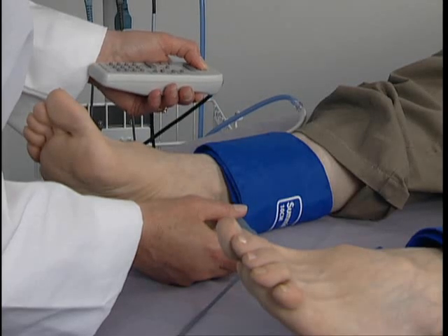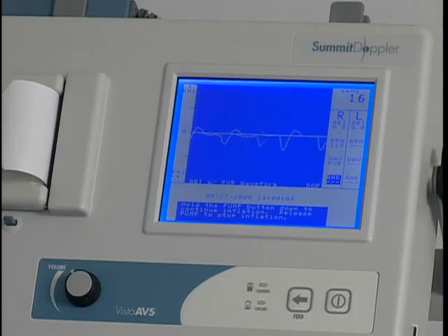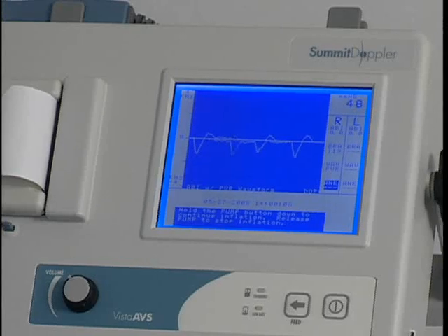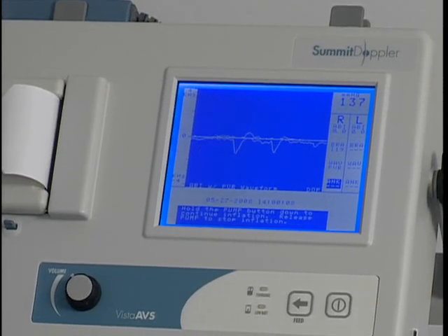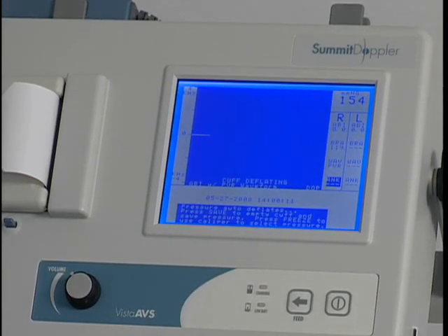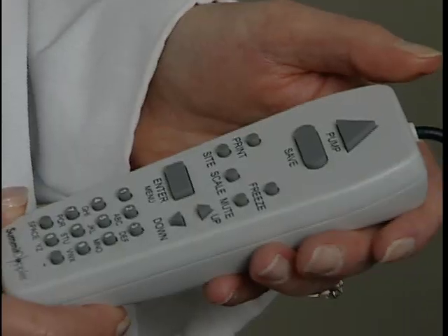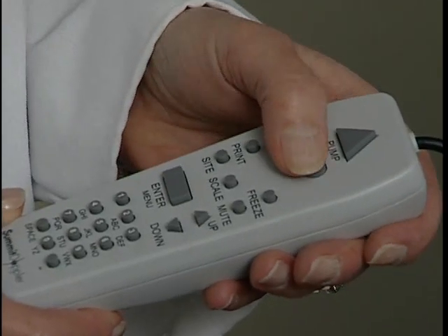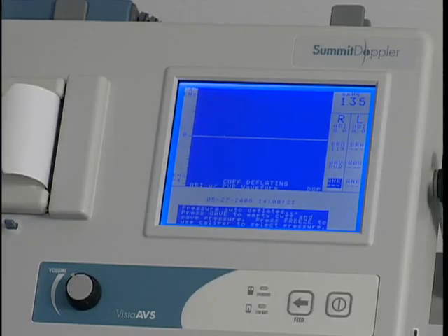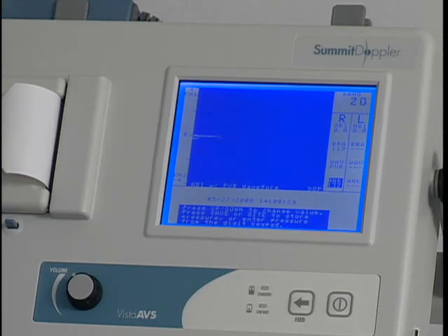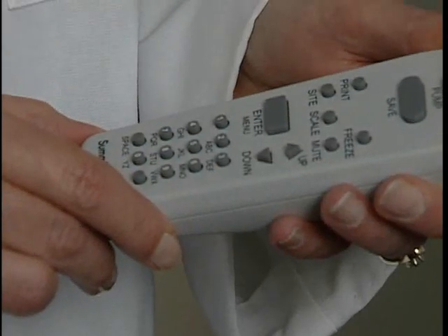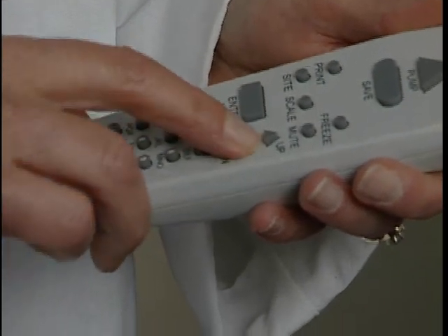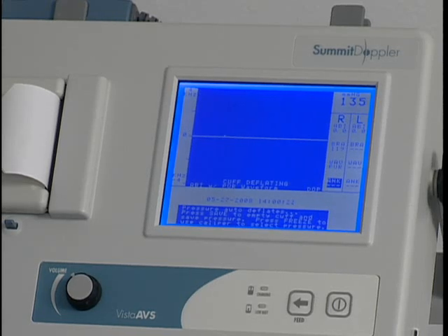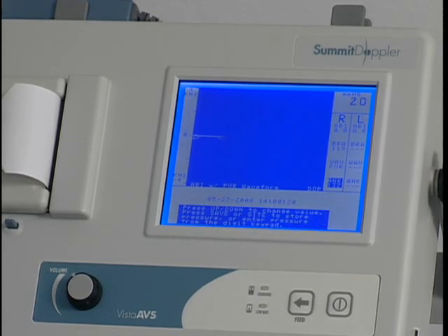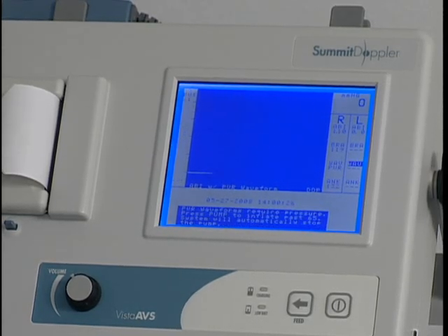Press and hold pump to inflate the cuff. Release the key once the pressure reaches about 20 millimeters of mercury above the occlusion pressure, and the cuff will deflate. Press save when you hear the first pulsation return. If you were late pressing save, adjust the pressure reading by using the up or down key as shown. Press save to record the systolic pressure and the marker will move to the next protocol location.